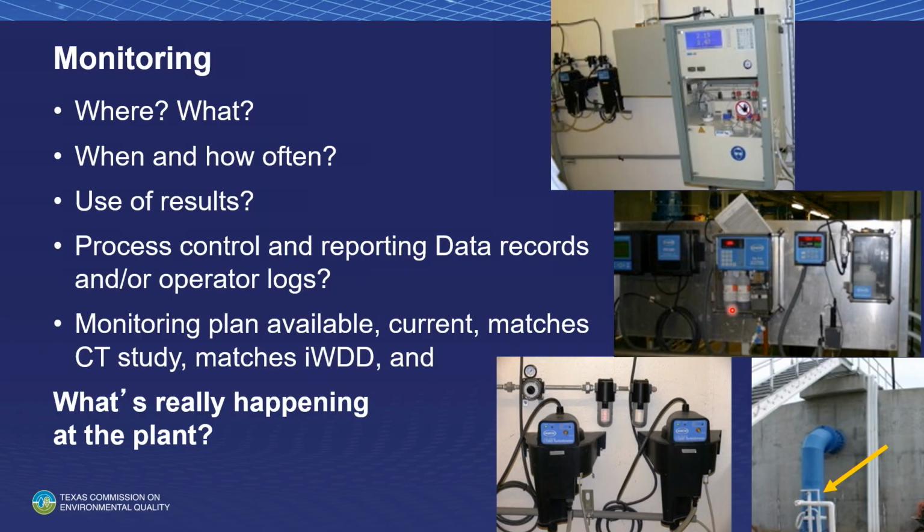Monitoring. Everything needs to be done according to the monitoring plan. If your monitoring plan doesn't tell you where you're going to do compliance monitoring, it must do that. The TCEQ rules do not require you to develop a monitoring plan that shows all your process control monitoring points. I think that plan is very important because that plan will tell you, what am I monitoring for? Why am I monitoring for it? What's my goal? What's my acceptable range? And what are my corrective actions? Okay? There is a directed assistance module, which I am so proud of that acronym.